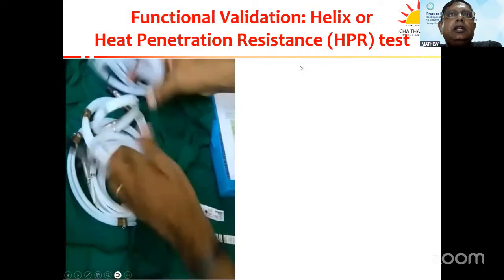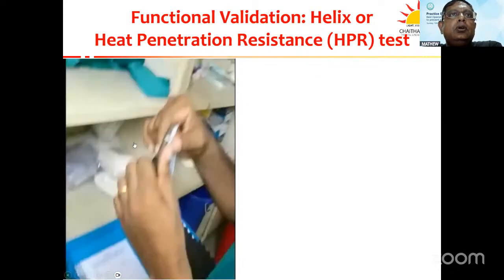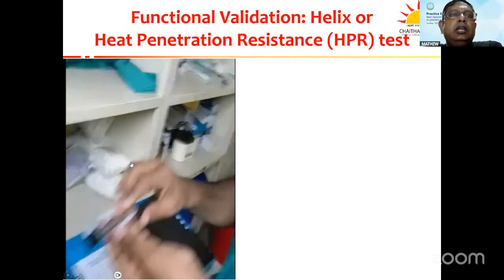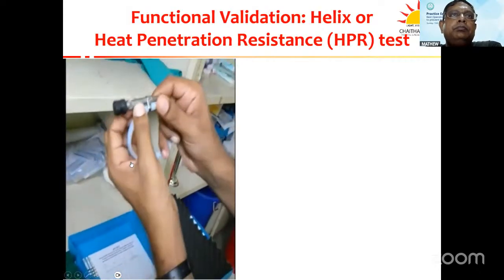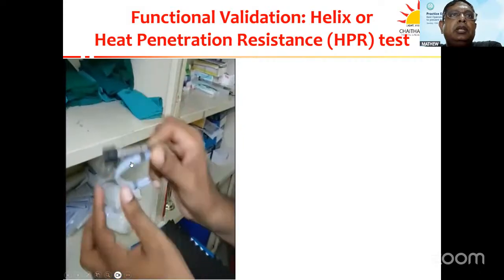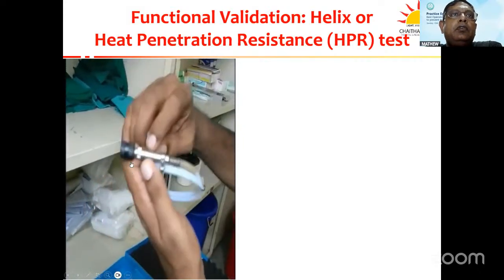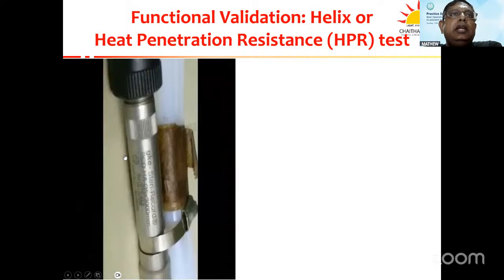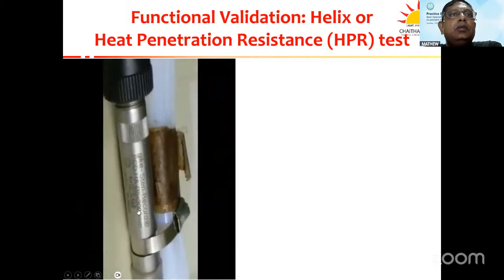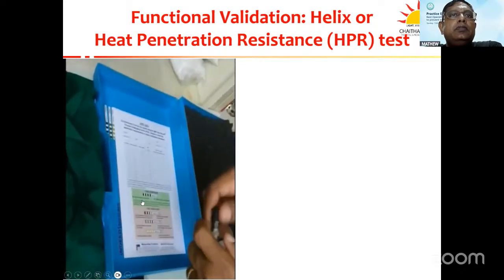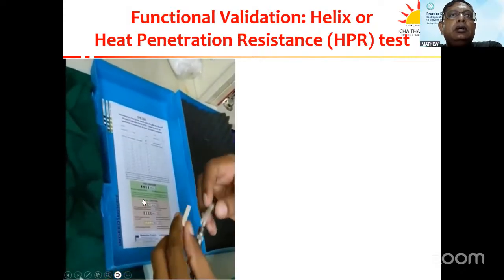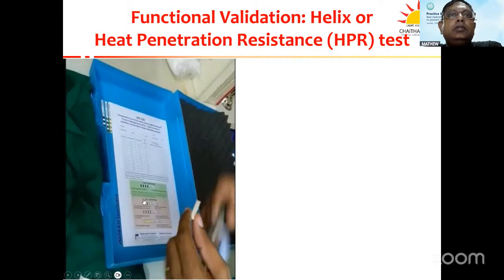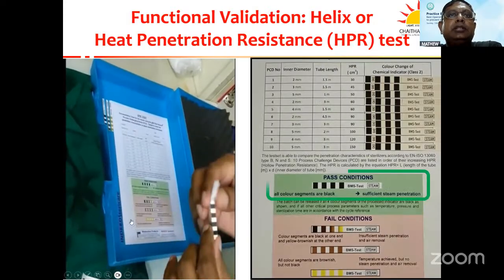And this is the functional validation, the heat penetration resistance test. These long tubes, which give different resistance to heat and steam penetration, have an opening at one end, and the indicator is placed at the other end. So this one will tell you what is the diameter of the tube and what is the length of the tube, and that has a calculation to show you how much resistance to heat penetration there is.